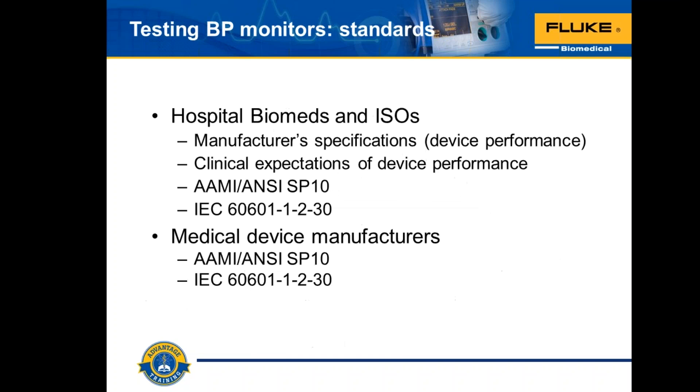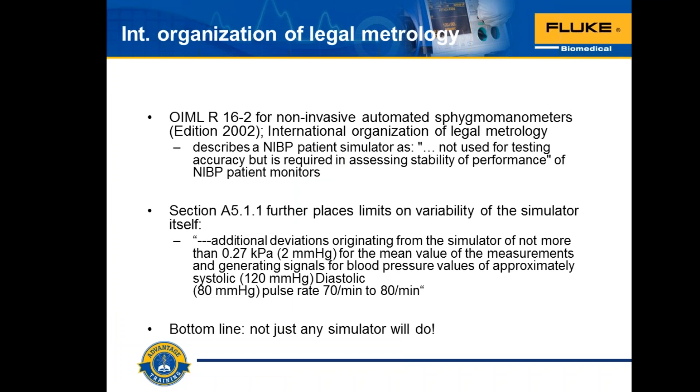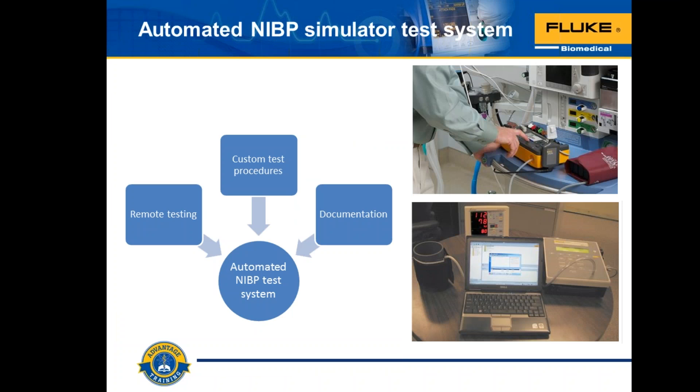Here's a picture showing our newest simulator, ProSim 8, alongside the BP Pump 2 and how it was connected. BP Pump 2 in this case is being controlled by ANSUR software in a template, making measurements in accordance with the functional and safety testing of the NIBP system. We really want a vessel — the cuff, hoses, and any valves inside the patient monitor — so we can properly pressurize and control as many variables as possible in measuring NIBP.